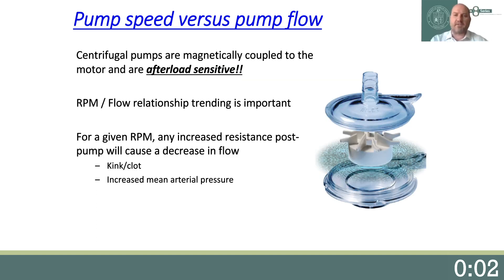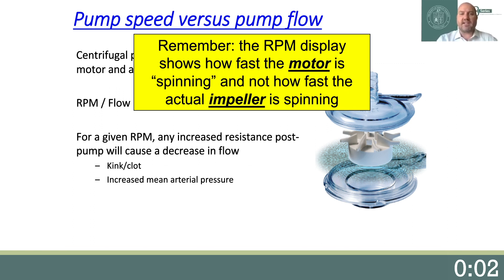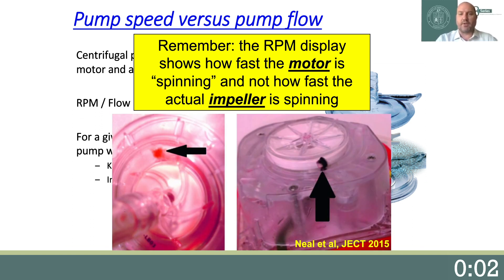Another essential concept of ECMO circuit monitoring is understanding the relationship between ECMO pump speed and ECMO pump flow. Centrifugal pumps are magnetically coupled to the motor and are afterload sensitive. Understanding and trending the RPM-to-flow relationship is important. For a given RPM, any increased resistance post-pump will cause a decrease in flow. A tubing kink, clot, or increased mean arterial pressure are some common causes of resistance that can cause decreased flow. Remember that the RPM display shows only how fast the motor is spinning, or the set speed, and not necessarily how fast the actual impeller is spinning. A clot on the impeller itself may cause drag, resulting in an actual speed lower than the set speed.